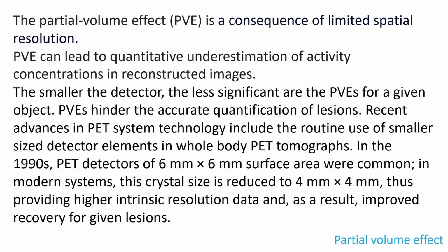The partial volume effect is a consequence of limited spatial resolution. PVE can lead to quantitative underestimation of activity concentrations in reconstructed images, and the smaller the detector, the less significant is the partial volume effect for a given object.